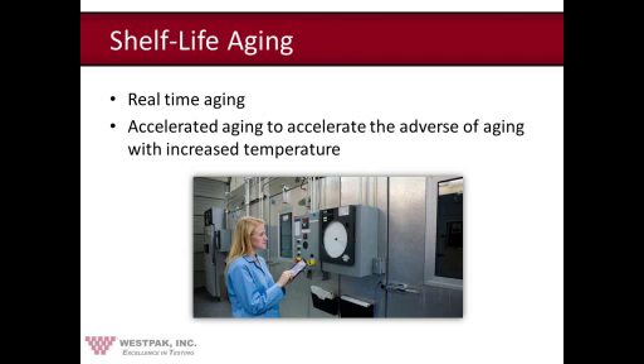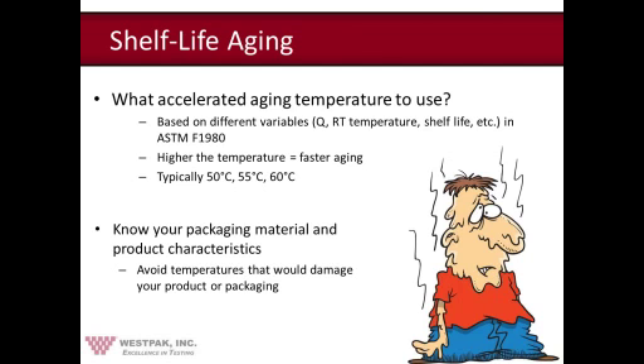Accelerated aging means accelerating the adverse effects of aging by storing the samples at an elevated temperature for a certain amount of time, and this will be equivalent to a certain shelf life at normal temperatures. What usually happens is the samples will go through distribution simulation testing, then aging, then sterile barrier testing to evaluate for any sterility breaches, and this should prove that your sample can maintain sterility throughout its intended shelf life. A question we get asked often is what accelerated aging temperature to use.